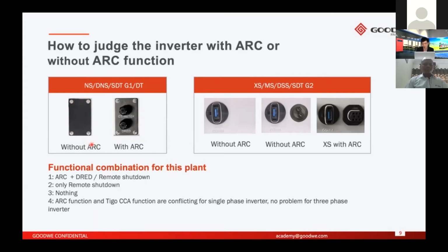The arc here is not the same as the FCR that I introduced yesterday. Here, the arc means anti-reverse current, which is similar to the export power limit. So if your inverter is NS, DNS, SDT G1, or DT, and the communication port is like this without the arc, your inverter can also do the export power limit, but it's more complicated. But if your inverter already has the arc function, with the communication port like this one, you can connect the CT or the meter to the inverter directly, so you can do the export power limit more easily.